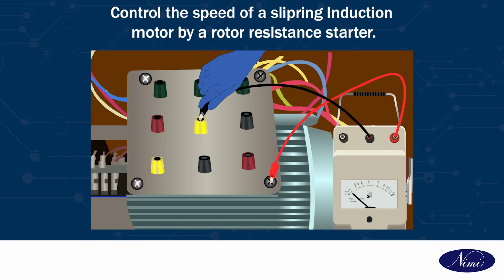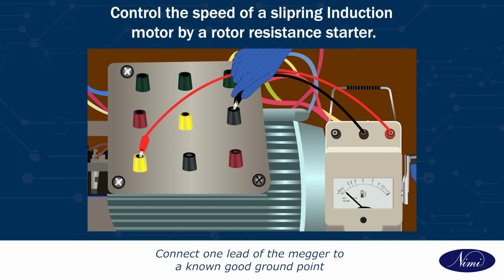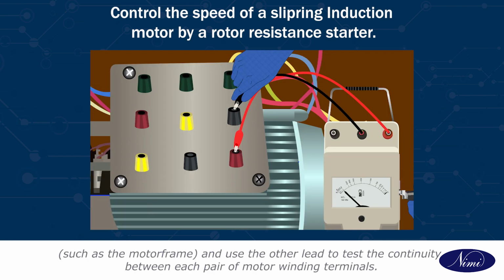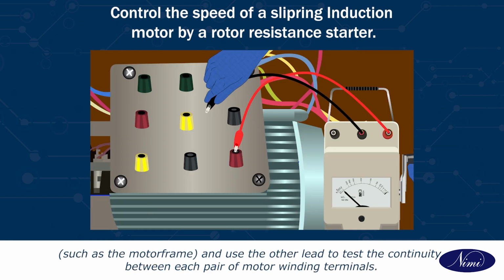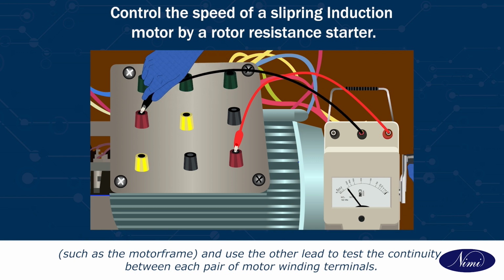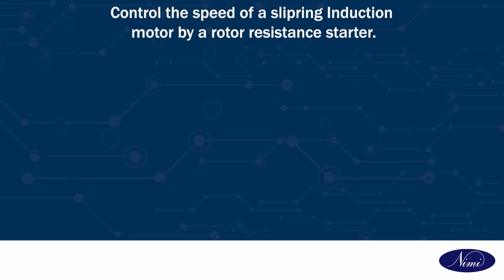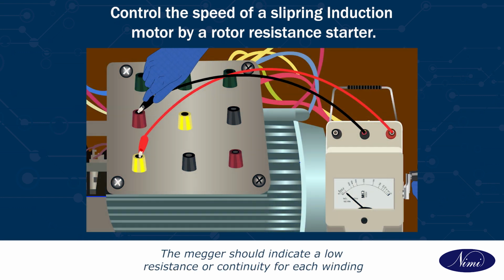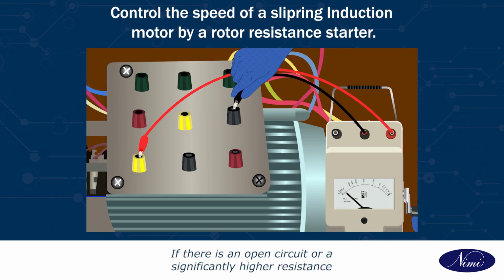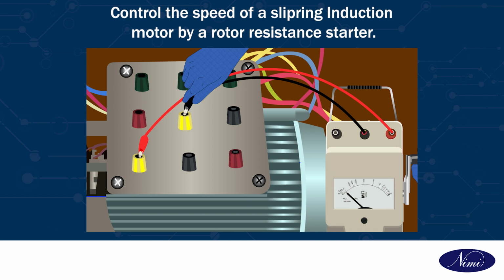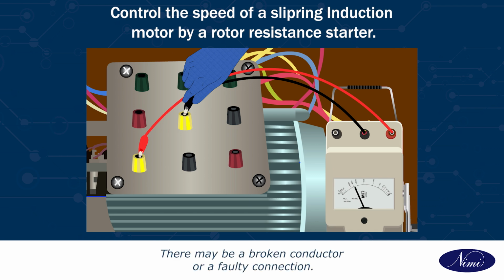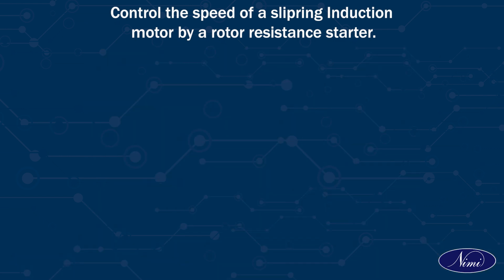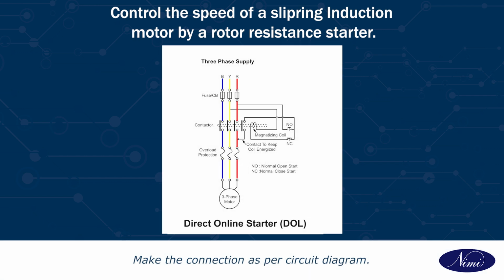Continuity test. Connect one lead of the megger to a known good ground point such as motor frame and use the other lead to test the continuity between each pair of motor winding terminals. The megger should indicate a low resistance or continuity for each winding. If there is an open circuit or a significantly higher resistance, there may be a broken conductor or a faulty connection. Make the connection as per circuit diagram.